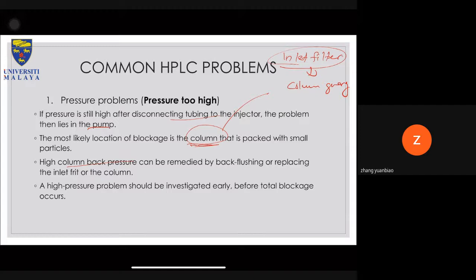Okay, high column back pressure can be remediated by back flushing or replacing the inlet frit of the column. If you recall, the inlet frit is a kind of filter that covers the silica inside your column and keeps it from getting out. You can replace it, but it might not be easy, because the column is normally made so that a normal user cannot reopen it. Of course you can open it if you want, but normally you can't.